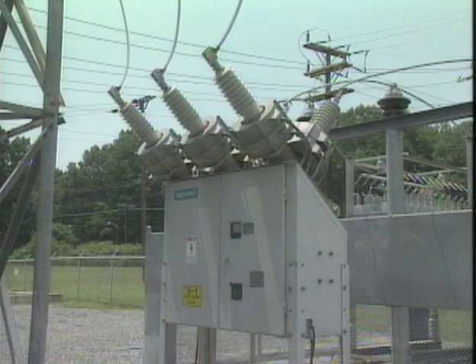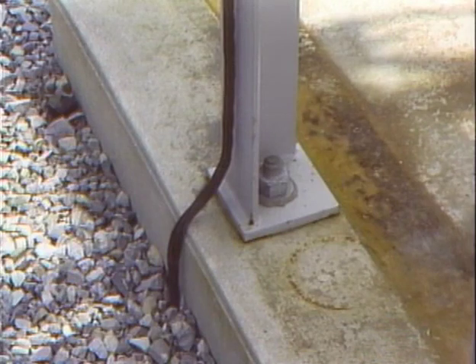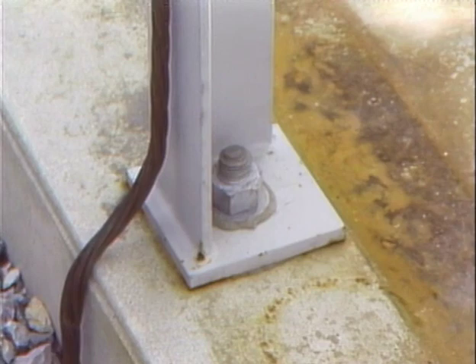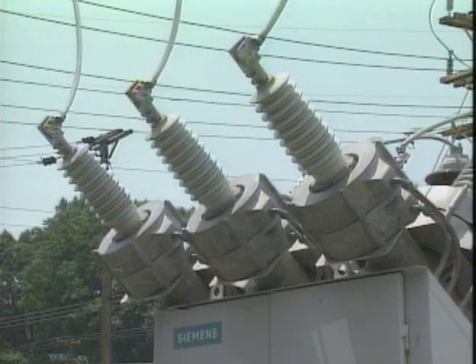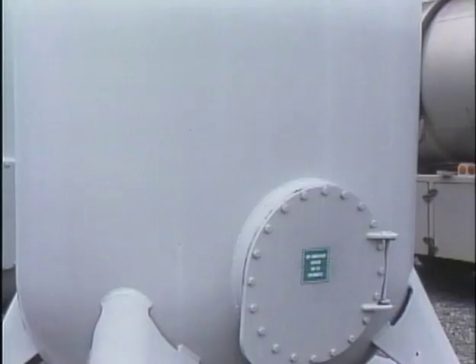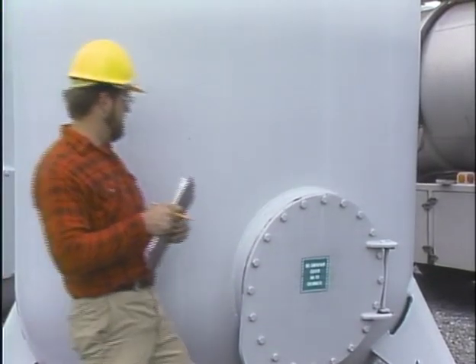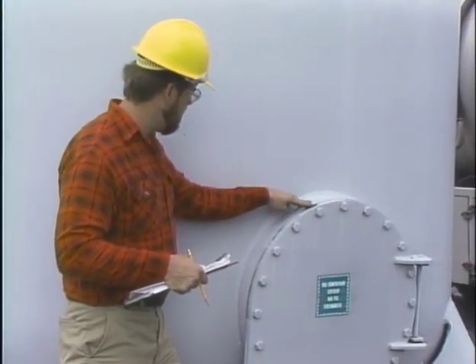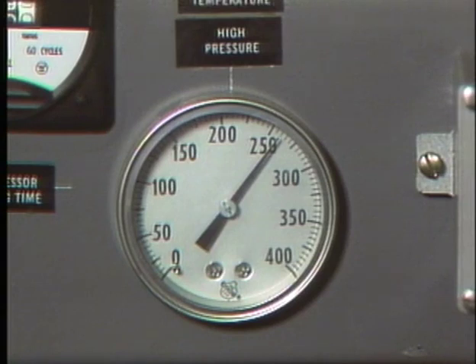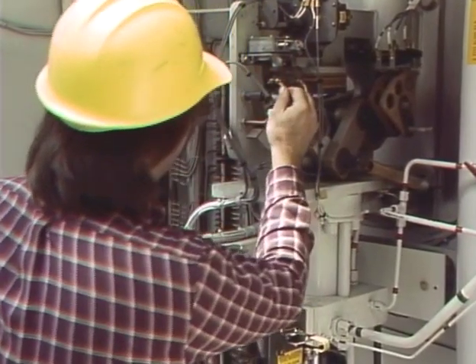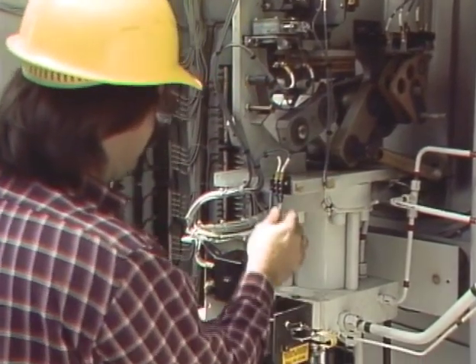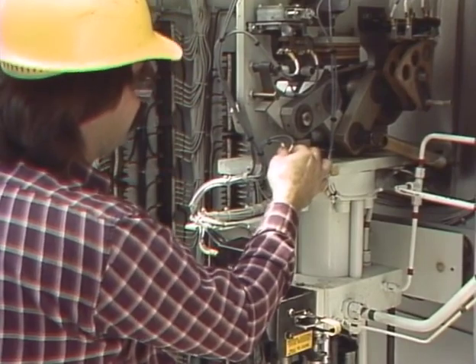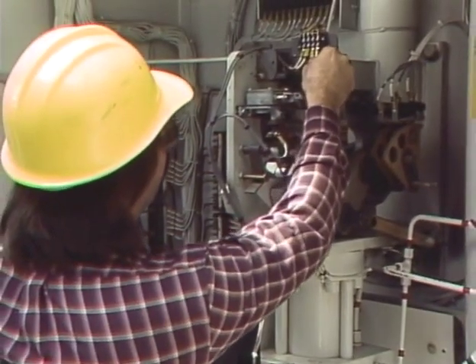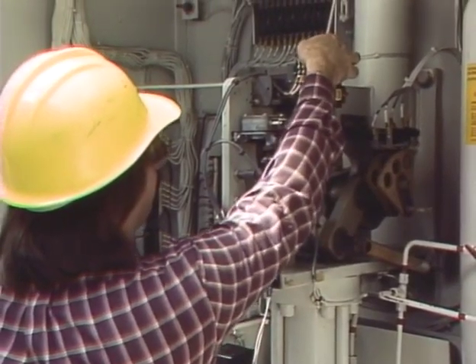Here are some of the typical mechanical checks of a circuit breaker. Ground cables are inspected for cuts or breaks or other signs of damage, and to ensure that ground connections are secure. The breaker's foundation bolts are checked to make sure that the breaker is securely bolted to the foundation. The bushings are inspected for any chips or cracks. Oil circuit breakers are checked for any signs of leaking around access covers, pipe fittings, bushings, and joints. Gas-insulated breakers are checked for proper gas pressures. All control wiring is inspected to make sure that it's not damaged, that all wire insulation is intact, that all wires are properly connected, point to point, according to the wiring diagram, and that all wire terminations are secure.